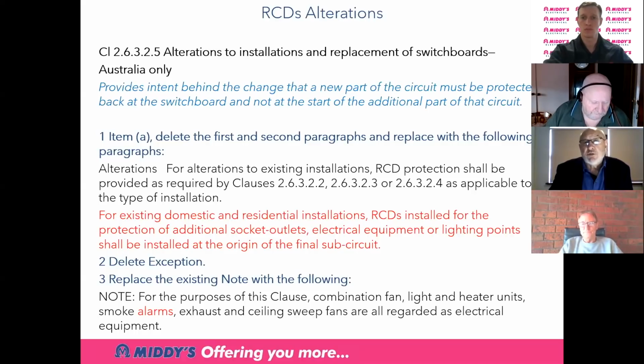Up till now, there was an option to actually add your RCD protection at the starting point of the alteration to the final subcircuit. And that is a little bit crazy if you think about it, because we're effectively allowing you to put a socket outlet RCD behind a piece of furniture or a curtain to provide protection for the new part of the circuit. So what we've decided is that we should be protecting the old part of the circuit as well as the new part of the circuit with RCD.